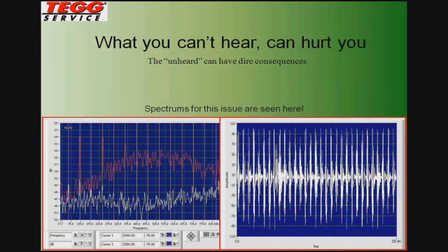And if we review that as far as what to expect, we have the first couple 60 hertz or 50 hertz harmonics rich in frequency content. That can clearly be seen here on the left. The difference on the right in the time domain is there is a lot of symmetry in the amplitude and spacing of the excursions that occur on top of the broadband white noise, whereas tracking in its purest form had the variations in the amplitude.